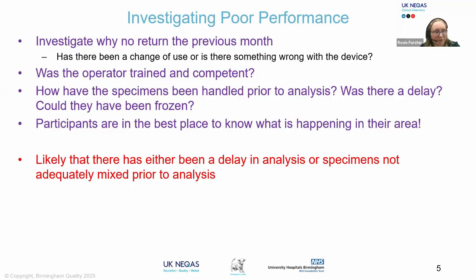And one point that we often reiterate to our participants is that although we can assist with troubleshooting, we weren't there on the day that the analysis was performed. So we don't know exactly what happened. Our participants are in the best place to know exactly what happened on that day and what went wrong. Often it's likely that the reason for poor performance in our point of care EQA schemes is that there's been a delay in analysis or the specimens, which are freshly prepared whole blood, have not been adequately mixed prior to analysis.